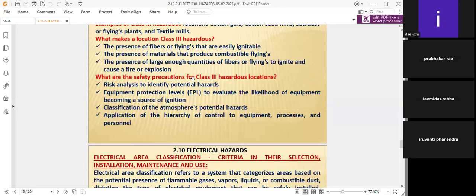What are the safety precautions for class 3 hazardous locations? Risk analysis to identify the potential hazards; equipment protection levels, that is EPL, to evaluate the likelihood of equipment becoming a source of ignition; classification of the atmosphere's potential hazards; and the application of the hierarchy of control for equipment, processes and personnel. These are very important areas.